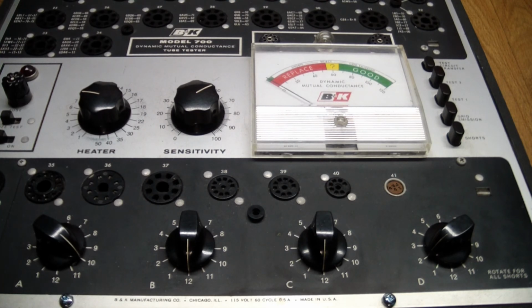Another thing that allays my suspicion a little bit is the symptoms the scope exhibited, and those were that every time I turned the scope on, and there are 4 traces, randomly 1 or 2 of the traces would exhibit noise, a lot of noise riding on the traces. Then I would power cycle the scope, not quickly, but rather letting it cool down for 5 or 10 minutes, turn it on, let it sit for another 5 or 10 minutes to have the tubes come up, and I would see the same thing, that again a random 1 or 2 traces would show noise, and they would always be different than the last time I observed it.